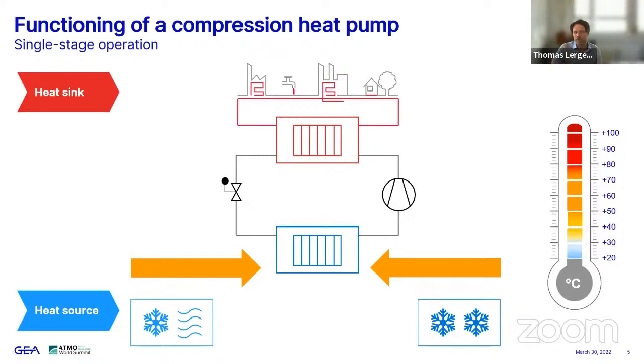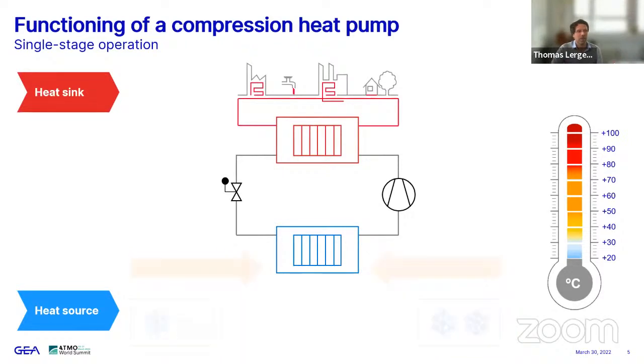If you don't have that kind of heat source, our heat pumps can obviously use different heat sources from the environment, for example, any liquid from the environment, from rivers, seas, waters, wastewater, brackish water, sewage water, or you can directly connect a cooling system to the heat pump. Then you have a simultaneous cooling and heating device.